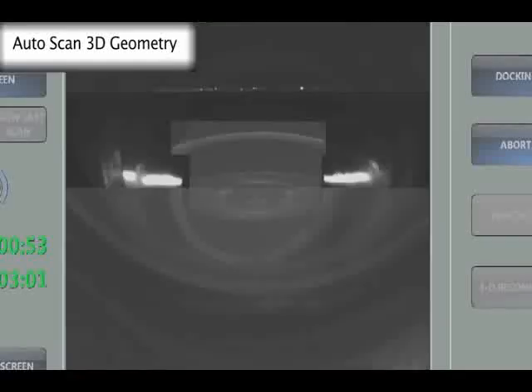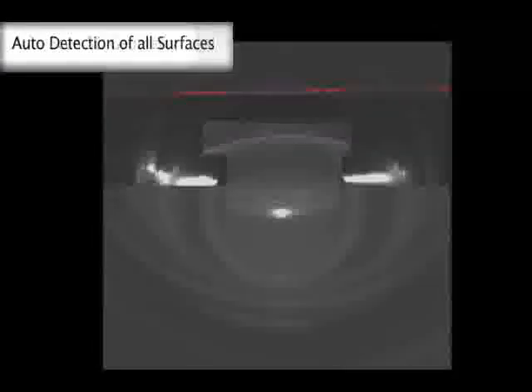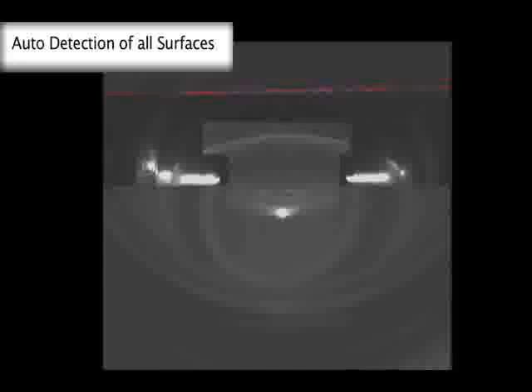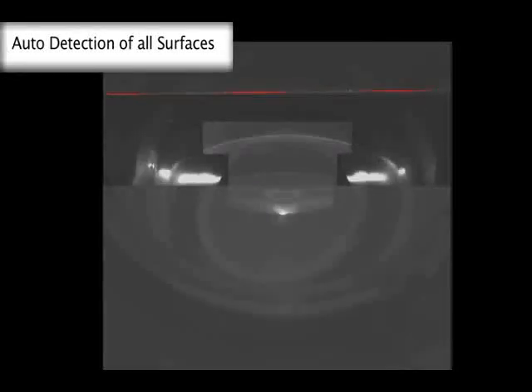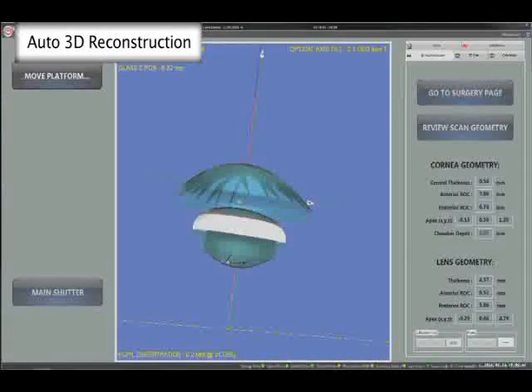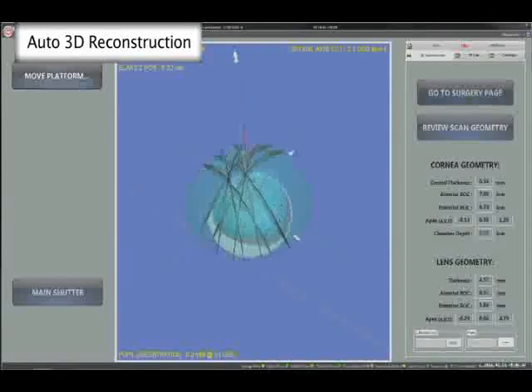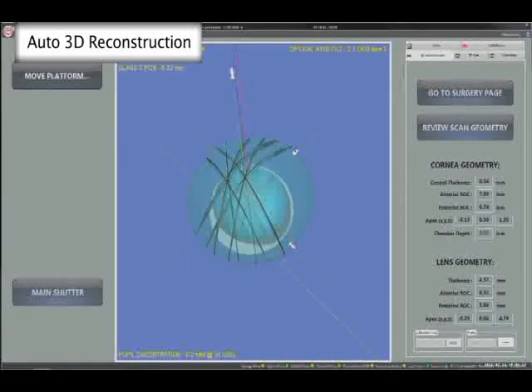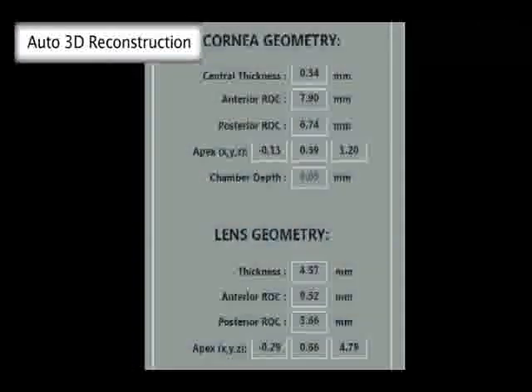Since the 3D CSI system produces images of high contrast and high signal-to-noise ratio, the images can be analysed automatically to detect the key surfaces: central and peripheral anterior and posterior cornea, as well as the anterior and posterior lens surfaces. Ray tracing is then used to produce a three-dimensional reconstruction of the eye, which will form the basis of the treatment patterns.